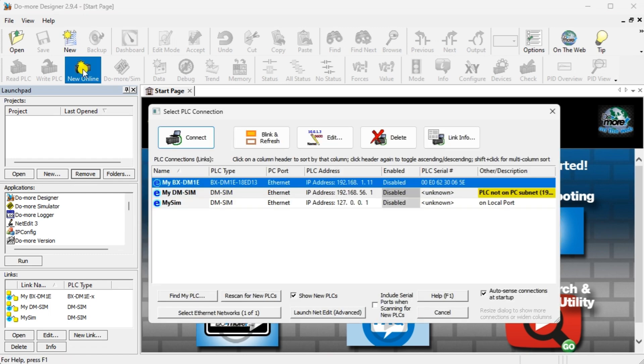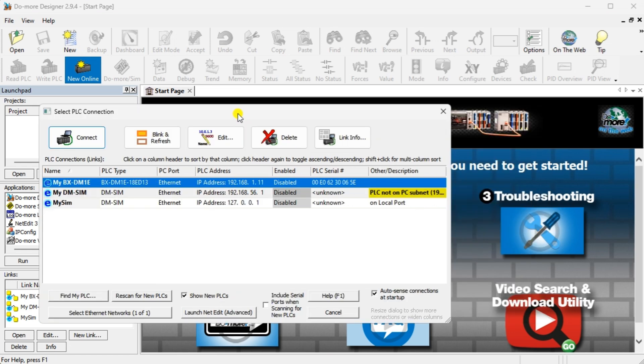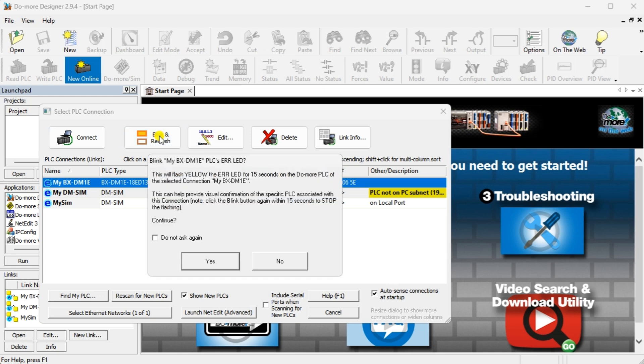Select the Online icon on the main ribbon menu. The Select PLC Connection window will be displayed — all devices that can be connected will automatically be displayed. You will see the PLC's IP address and physical MAC address. If you're unsure if this is the controller you want to program, select the Blink and Refresh button. This will blink the error LED on the CPU yellow for 15 seconds. A warning message will appear — select Yes to start flashing the CPU LED.